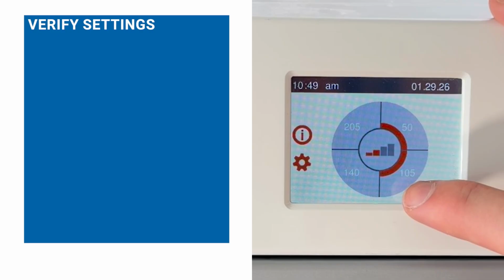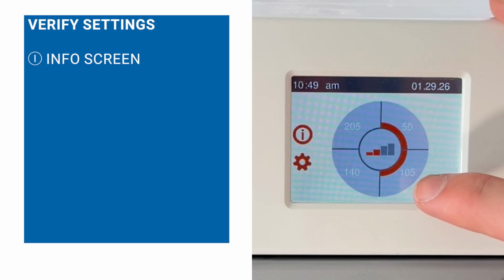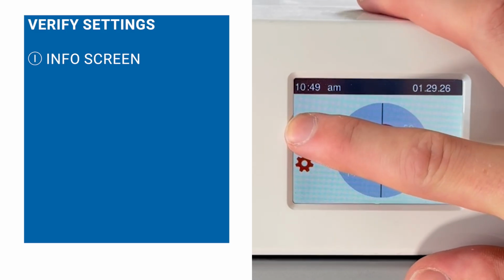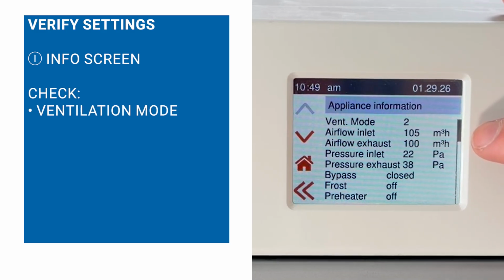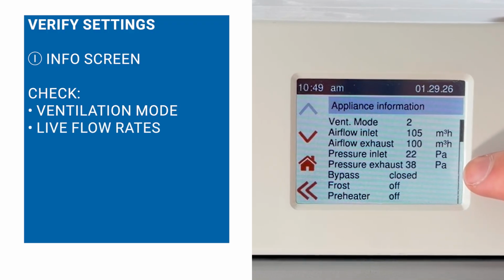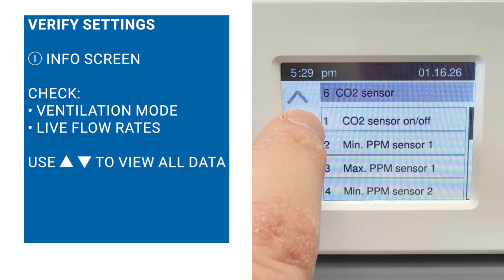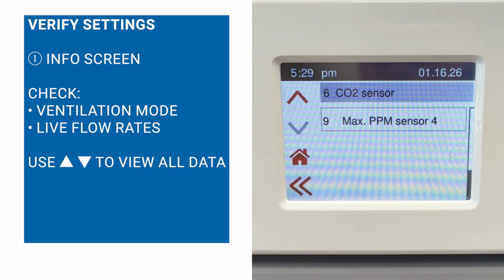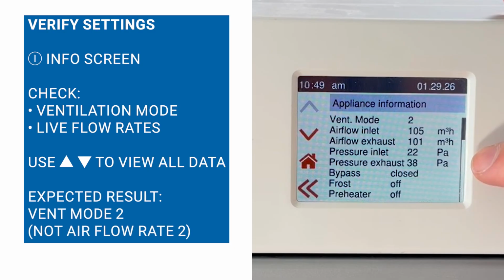Verify that the unit is in fact on the correct setting and no external controls are influencing the unit by navigating to the info screen, the eye on the home screen, and finding the ventilation mode and the live flow rates. Use the up and down arrows to find all data points. The unit should show it is in vent mode 2.